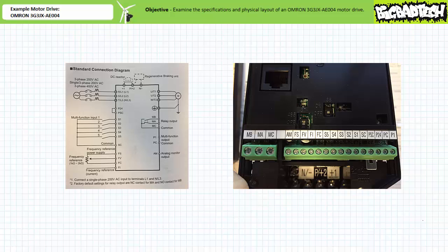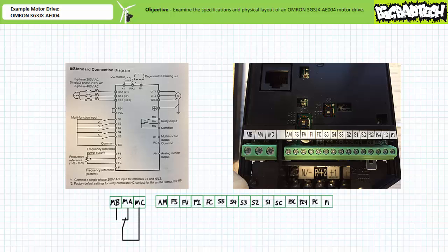To examine the rest of the connections, we need to remove the front plate. Note two micro switches, S7 and S8, respectively configure the motor drive for serial communications and emergency shutoff functions. Note the default state of these switches. Additionally, note the open front plate has exposed manufacturer test points and two rows of accessory terminals.